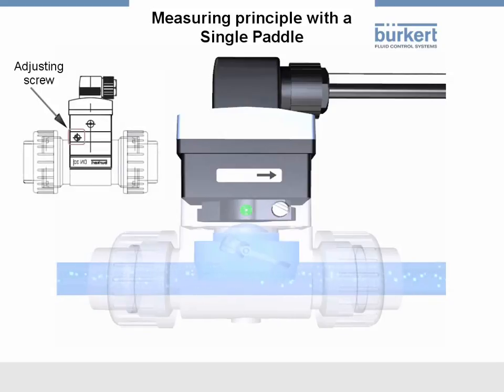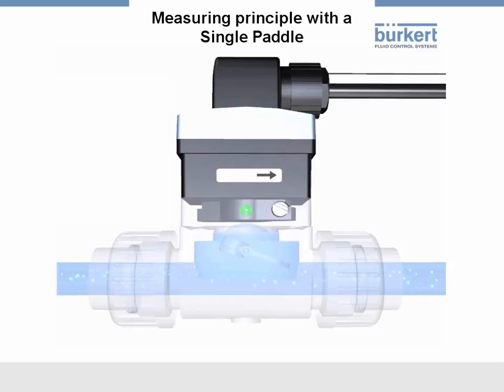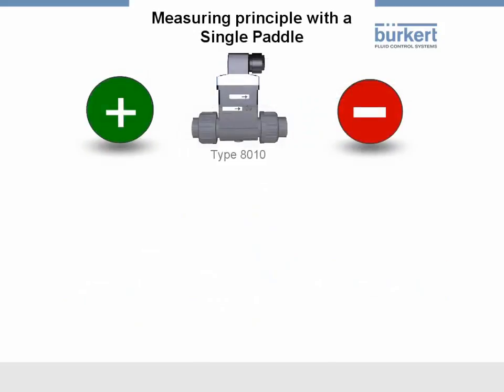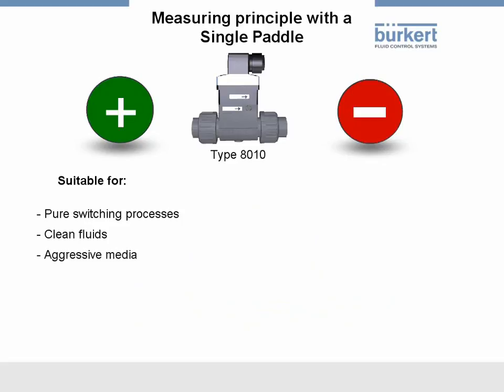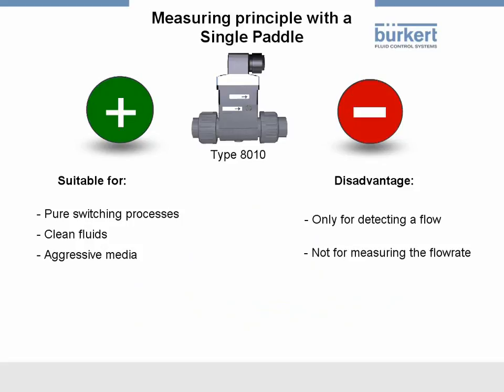An adjusting screw makes it possible to set the switching point to different flow rates, therefore allowing adaptation to the respective application. The output is available in the variants normally open, NO, and normally closed, NC. A flow rate greater than the set value closes or opens the contact. This method is suitable for pure switching processes in clean fluids. Due to the encapsulation of the magnet and the electronics, it can also be used in aggressive media. However, this method can be used only for detecting a flow and not for measuring the flow rate.